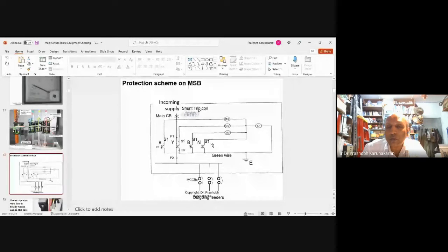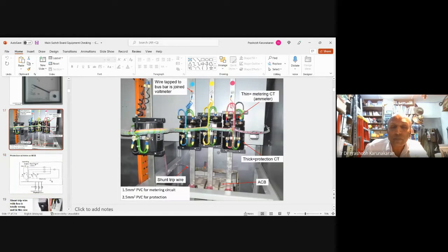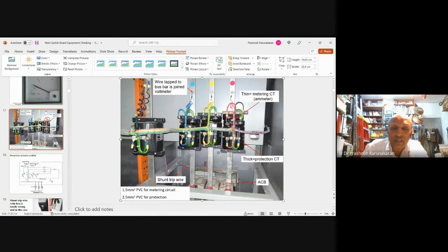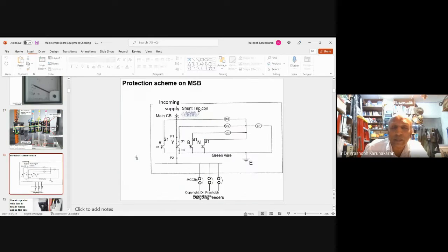So red, yellow, blue, neutral - the red, yellow, blue CTs. What is this S1, S2? Look here - you can see this one's name is S1 and S2, the two terminals. If you look here, the S1 of red, yellow, blue go to the 3 different OCs. Coming out of the OC, they're coiled up and joined to the neutral S1.